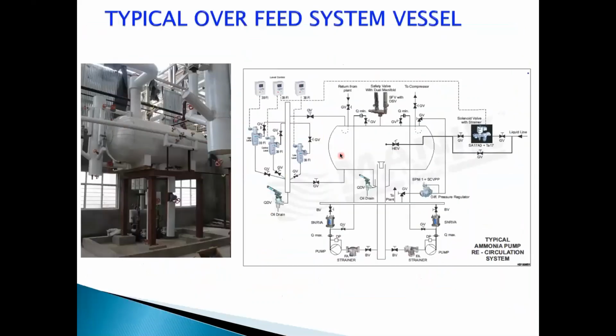So this is a liquid overfeed system, or pump overfeed system. The LP vessel or the pump recirculation vessel is the most critical part. Here we have a vessel in which expanded liquid is stored, and through this pipe it's fed to the ammonia pumps. Through the ammonia pumps, the liquid is fed through this line to the system, and the liquid and gas will come back into this LP vessel. Liquid will fall down and gas will go back to the compressor.